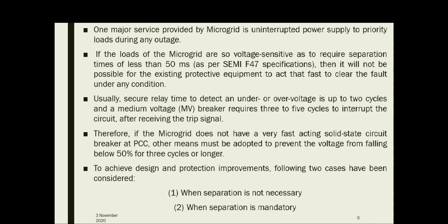One major service provided by the microgrid is uninterrupted power supply to priority loads during any outage. If the loads of the microgrid are so voltage-sensitive as to require separation times of less than 50 milliseconds, it will not be possible for existing protective equipment to act that fast to clear the fault under any condition. Usually, secure relay time to detect an under-voltage or over-voltage is up to two cycles, and a medium voltage breaker requires three to five cycles to interrupt the circuit after receiving the trip signal.